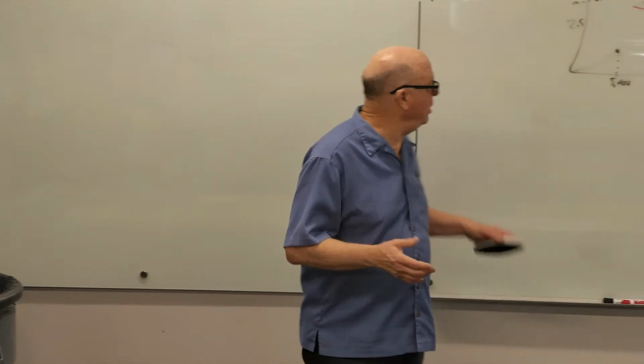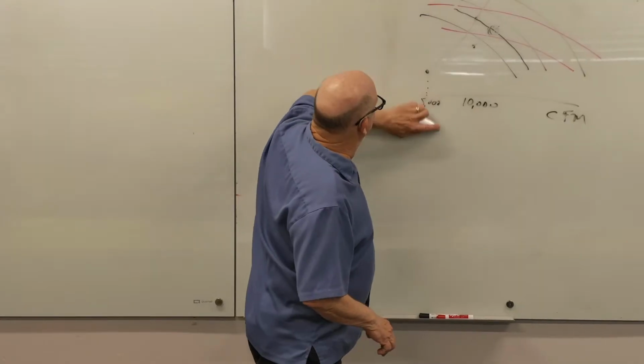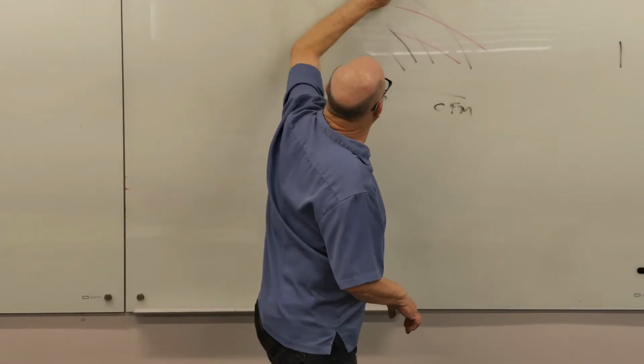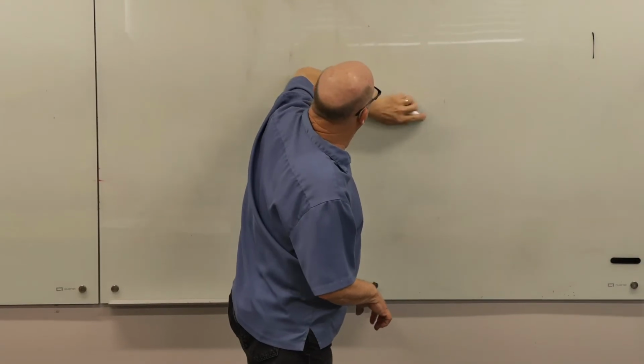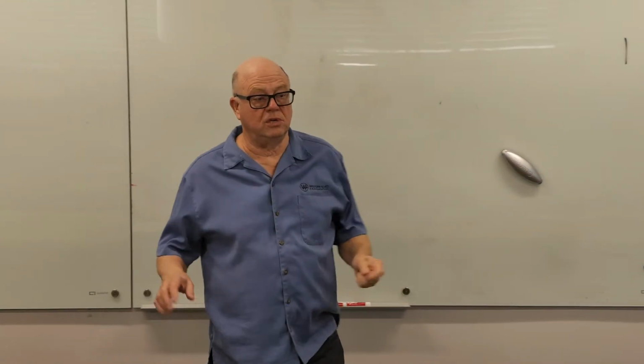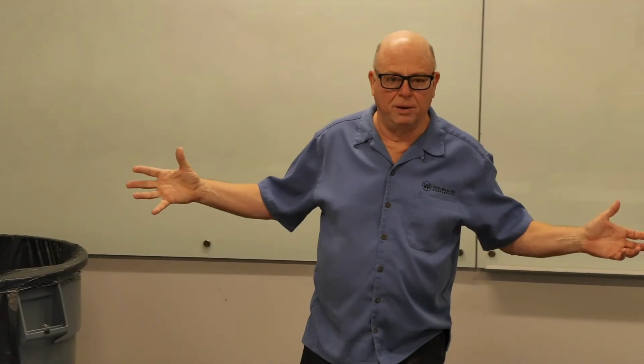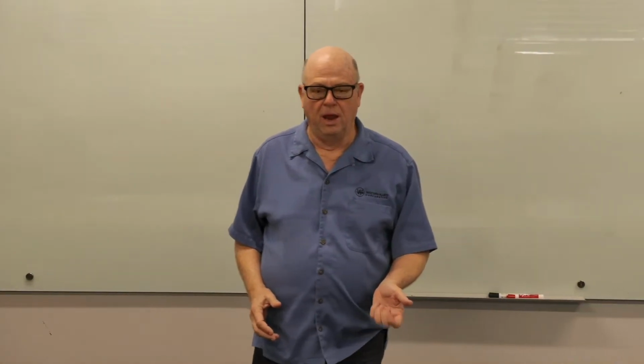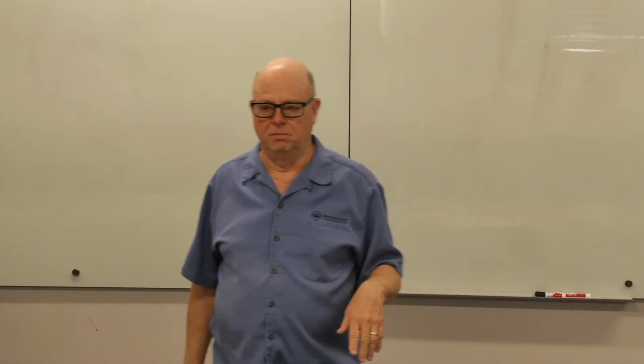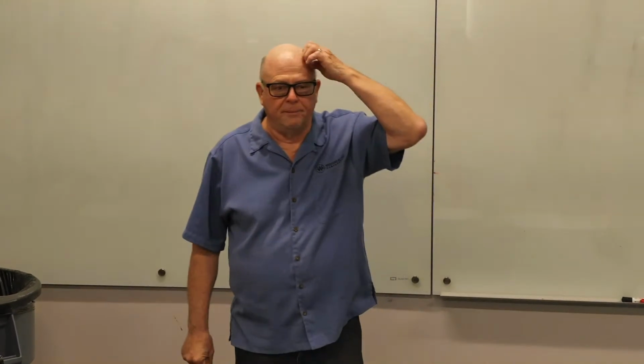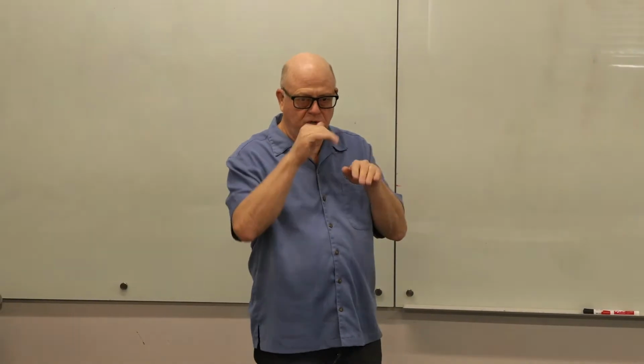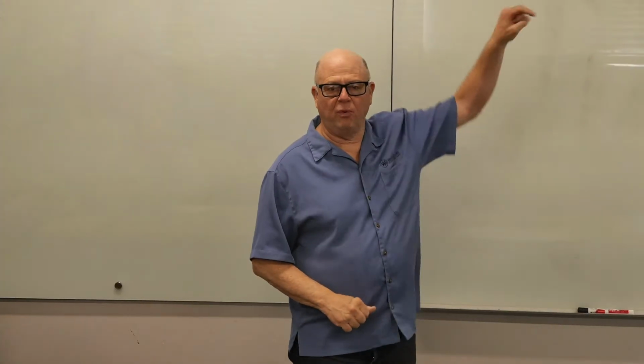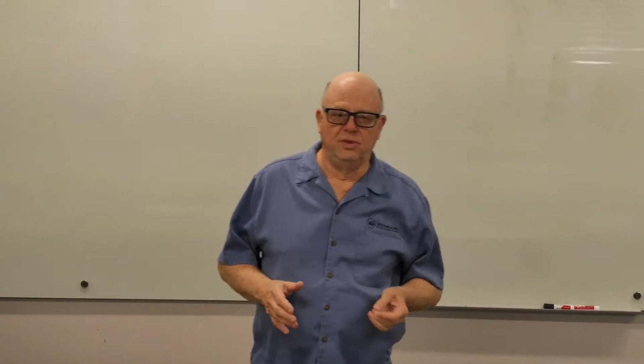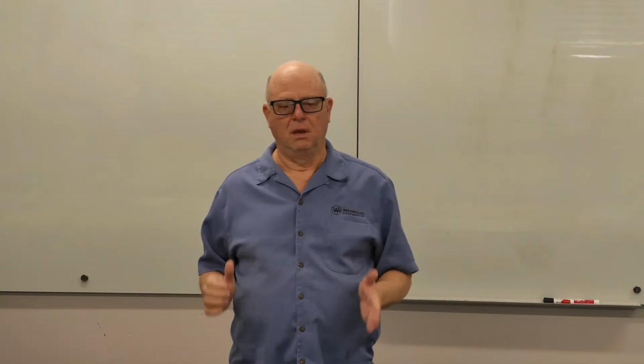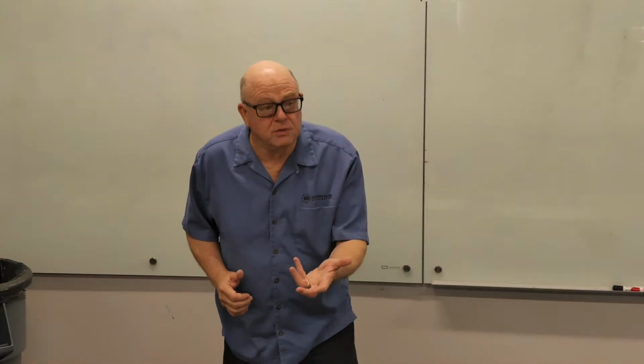A variable speed drive changes the hertz. You all know that in North America we use 60 hertz power. Almost any place that was part of the modern British Empire uses 50 hertz power. And other places, it depends on who conquered them. Like the Philippines uses 60 hertz. The hertz relates to the period of the waveform, and what a variable speed drive does is cut it down.